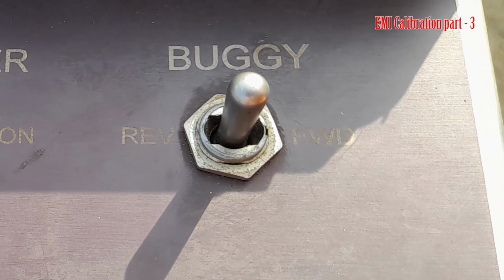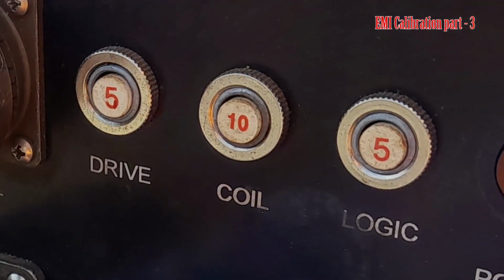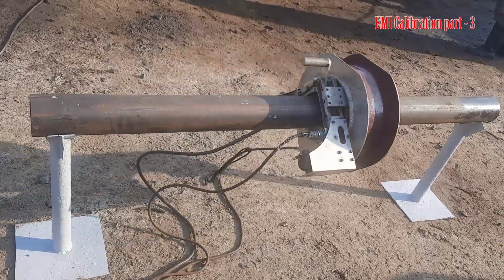And the third one is buggy control. Just move the buggy forward. If the buggy is not moving, then your cable is loose or your buggy speed is 0. So check these two things, buggy speed and cable. There are 3 breakers: one for the drive and one for the coil. If there is any short, the breaker will turn off. In that circumstance, also check the breaker in the coil case and the drive case.